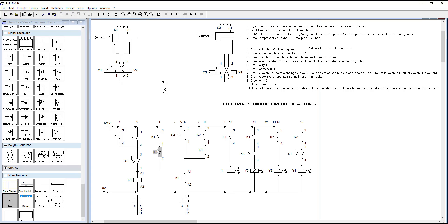This part indicates the memory unit. The trick is: whenever we use relay K1, always use an open switch of K1 and a closed switch of K2, where K2 is the next relay. When the push button is pressed, current flows through relay K1 and K1 gets energized. When K1 gets energized, it closes all the open switches and opens all the closed switches that share its name. So the K1 open switch gets closed, and the K2 normally-closed switch gets opened.